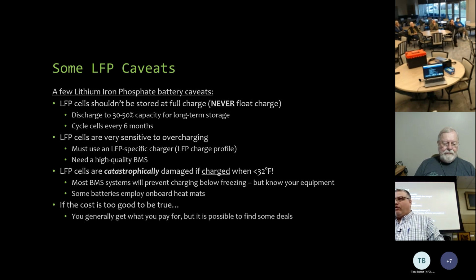They are very sensitive to overcharging. So a couple of things: you do need a high quality battery management system. Most of the off-the-shelf batteries do include that. But you also need to use a lithium iron phosphate specific charger that has that charge profile for a lithium iron phosphate battery. It's going to deliver the right amount of current during what's sometimes called the bulk charge phase, and then in the top-up phase, it's going to transition to a constant voltage mode to bring it up to a full charge.